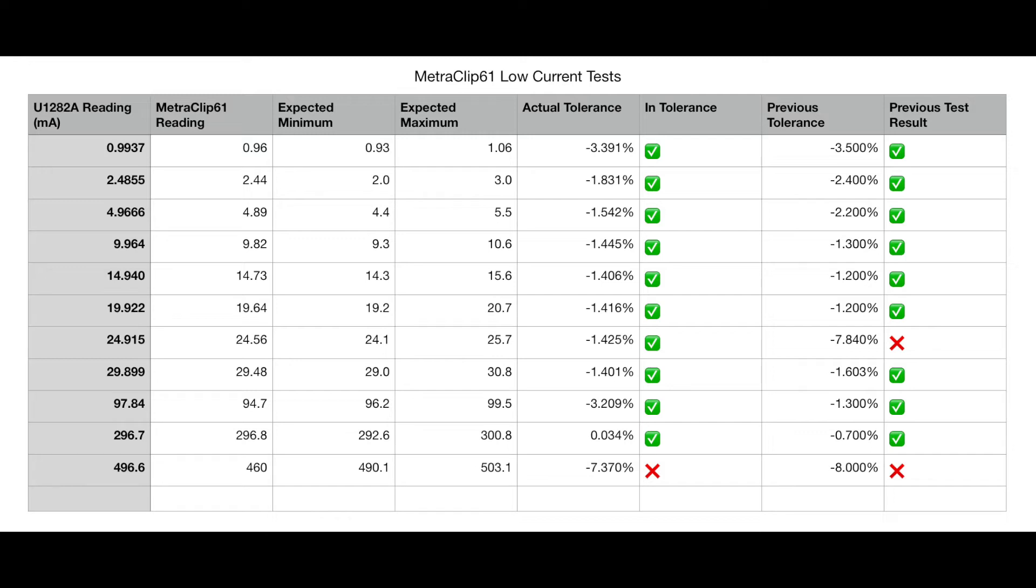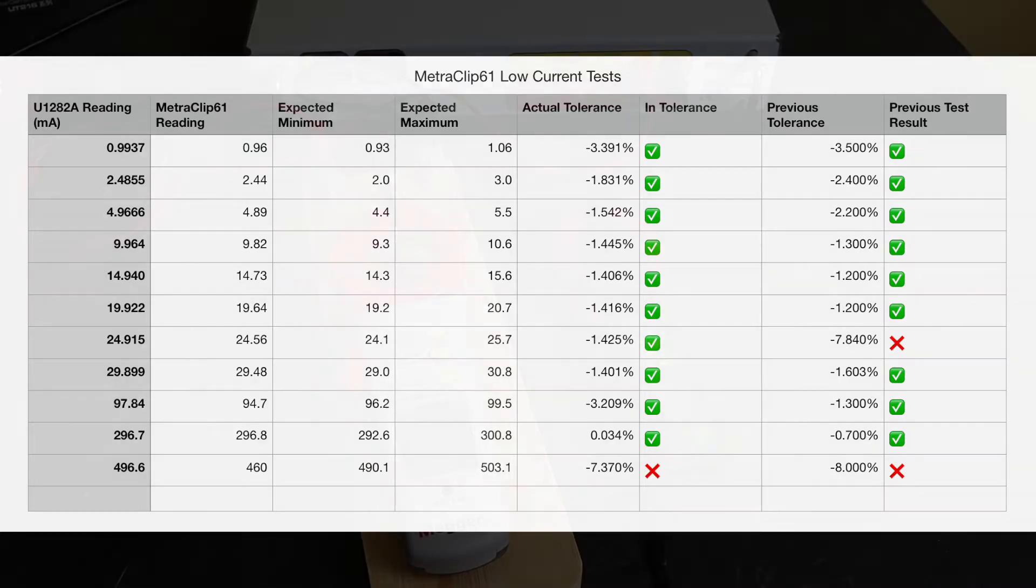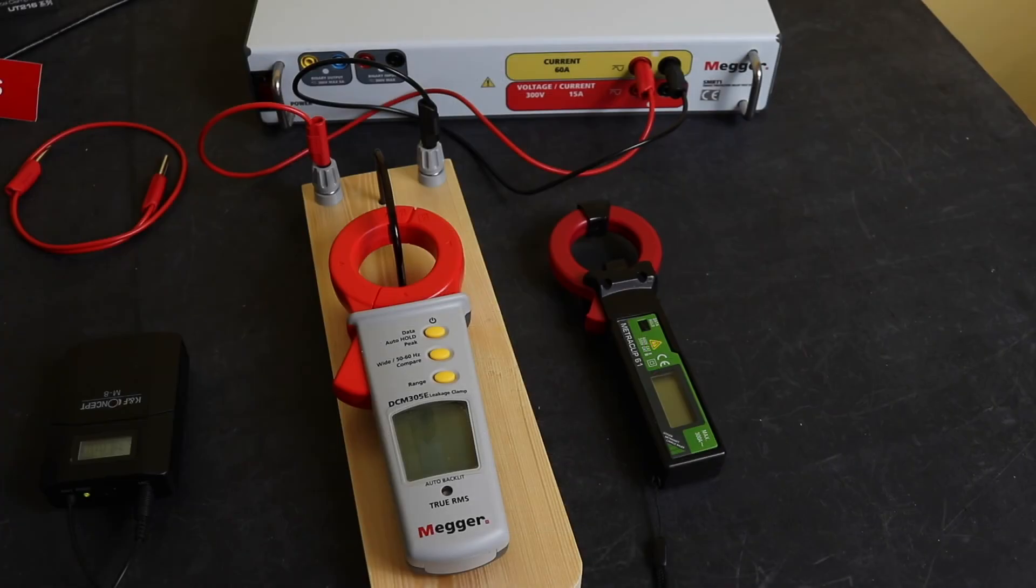Again, if you look at them, there's no real major differences between the tolerances. I guess there's a little bit at 100 milliamps. Again, it was minus 3% this time around but 1.3% last time, but yeah, nothing majorly significantly different. So not sure whether there is an issue with that DCM305E at a certain range or if there's still an issue with my test setup.